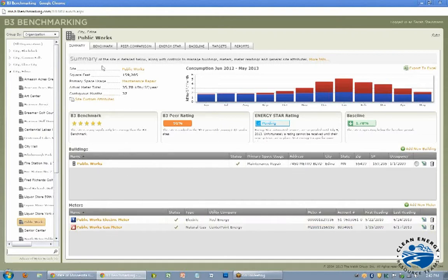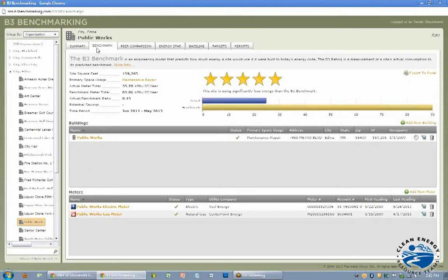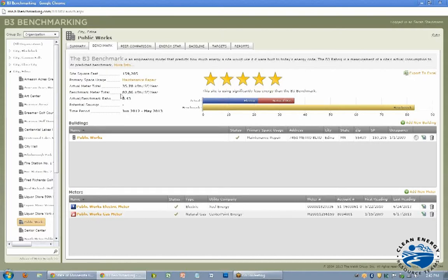Right here we have the Benchmarking tab, and benchmarking is a formula that you get from taking your KBTU, so 1,000 BTU per square foot per year. So you enter in the square footage of your building, and then you enter in the energy use, and it calculates the actual KBTU per square foot per year. And then through an engineering model, they determine what a building like that would use if it was based on the current energy code.